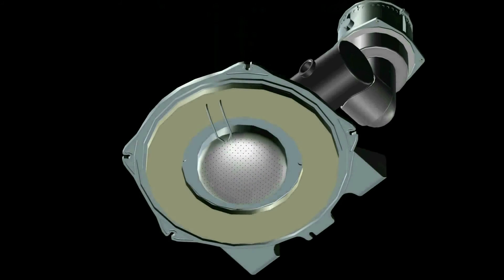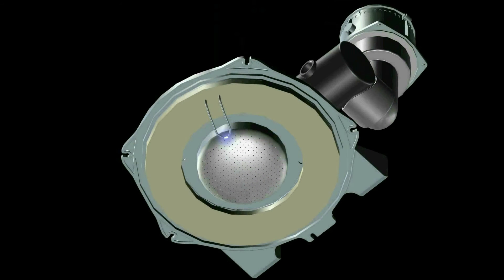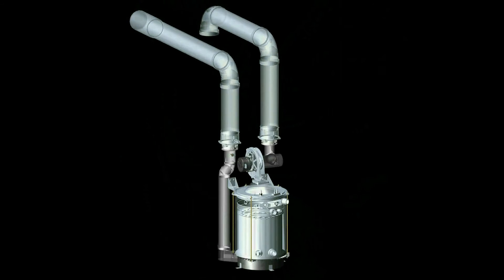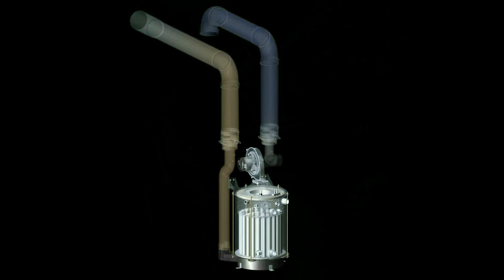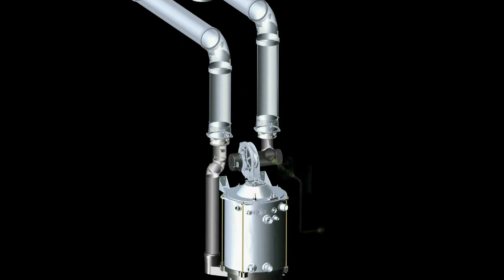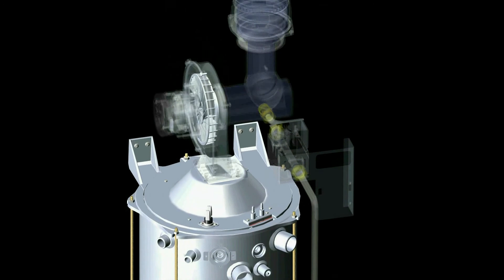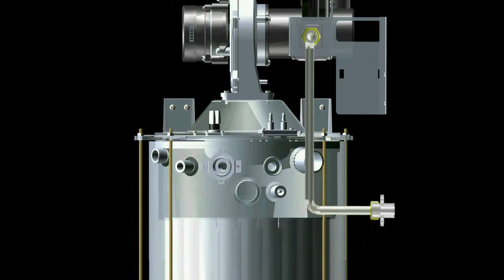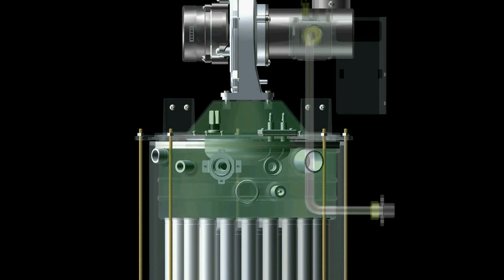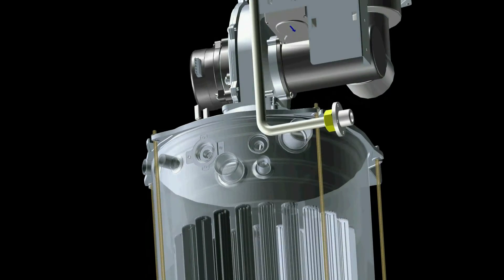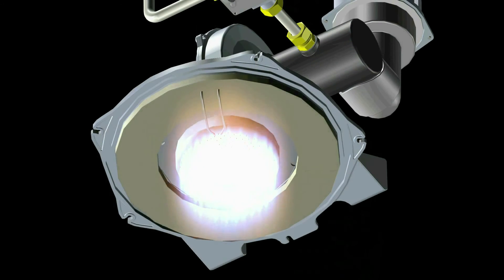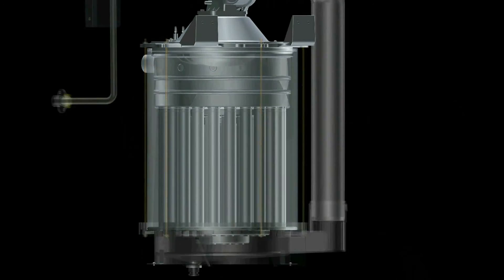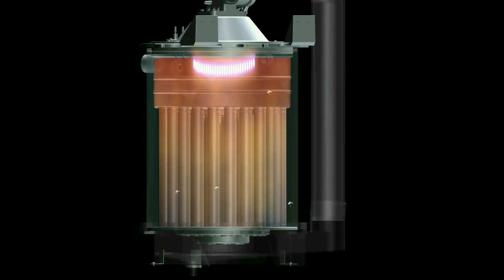Power is supplied to an electric transformer which creates flame consistently on an igniter. Now you can see the image in which air is moved into the product and gas is discharged to outside. A blower is operating and the gas valve is opened to mix gas with inhaled air. The mixed gas enters inside the burner. At this time, the entered mixed gas and the flame created on the igniter are ignited. If the flame is sensed, the flame is extinguished after 2 seconds and ignition would be operated normally.